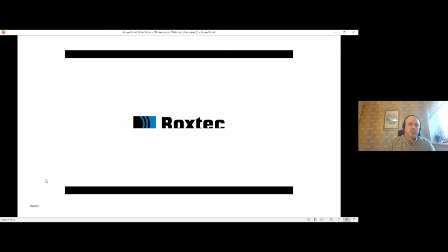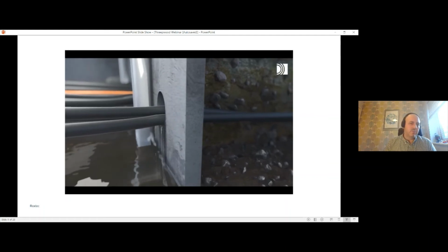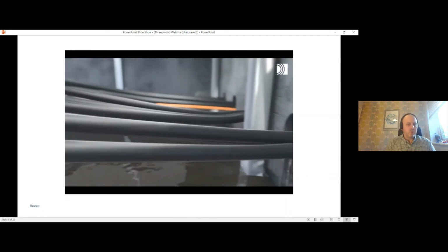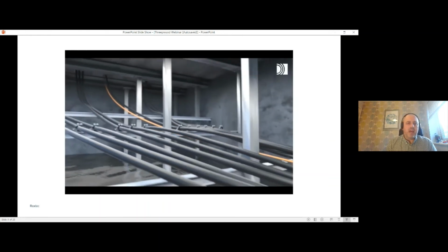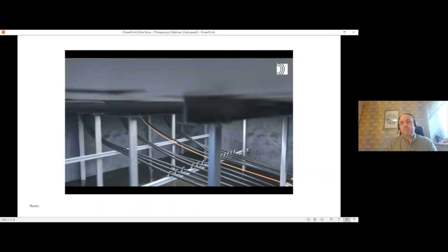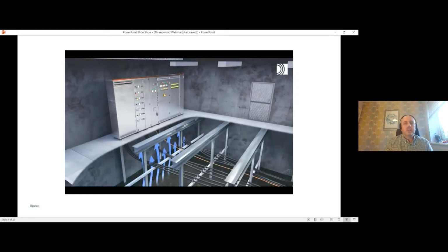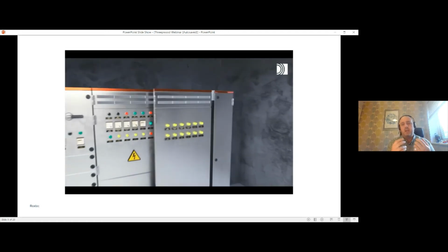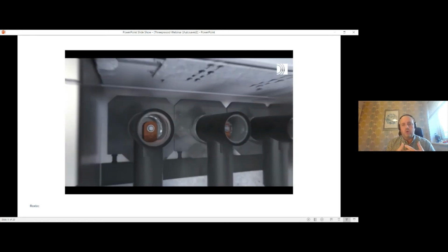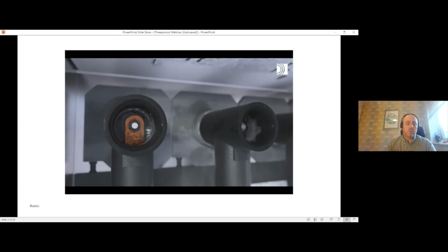But for me, when we're talking about badly sealed buildings, we're talking about water ingress, dust, dirt, humidity, pollutants. That has a significant impact on inception and acceleration of potential partial discharge activity on switchgear, whether that's an internal failure or treeing on the surface of materials. But what will eventually happen with this is a failure.